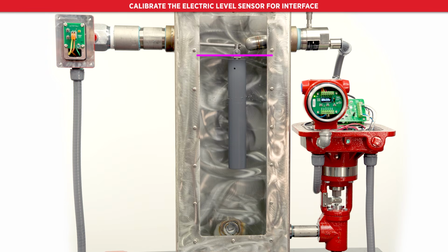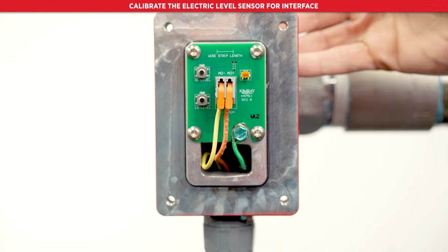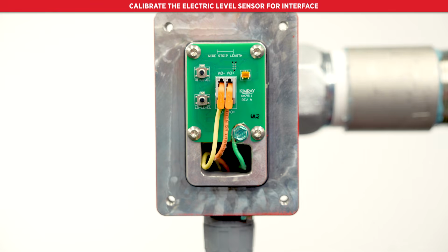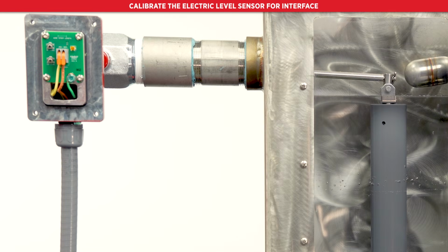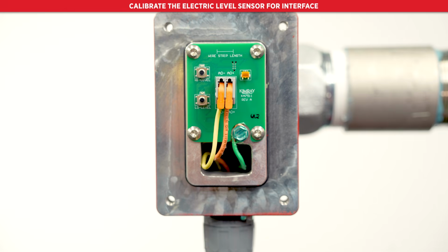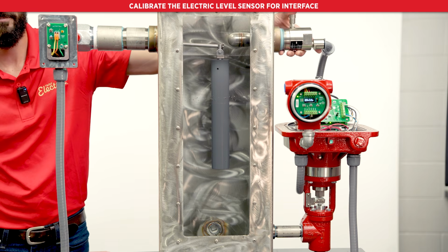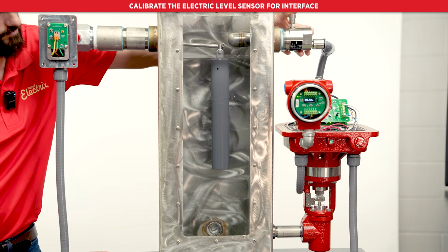Once the level is above your displacer, shut off the incoming flow to the vessel to maintain liquid level until the calibration is complete. Now press the high level button. It will take 45 to 60 seconds to run the calculation. Once complete, the low level LED will begin to blink. Now empty your vessel's liquid until the water level is below the displacer.